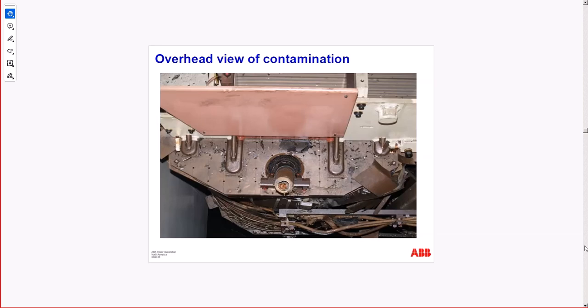So the oil came out, which means you could have sharp filings in the transformer. Very dangerous. They collect electric field and can get up to 10 kilovolts on the edge, penetrating even Nomex and going through.